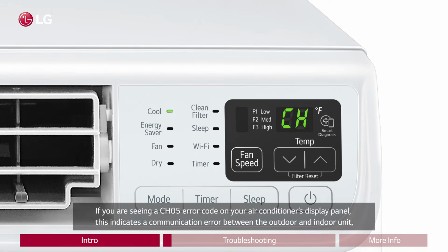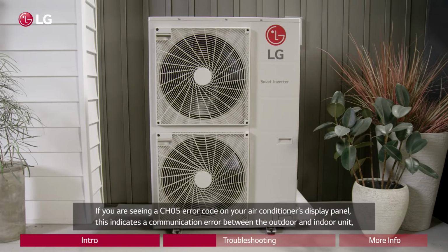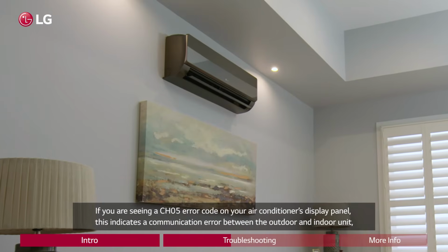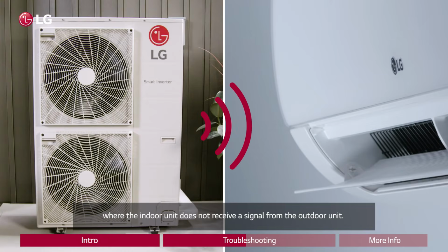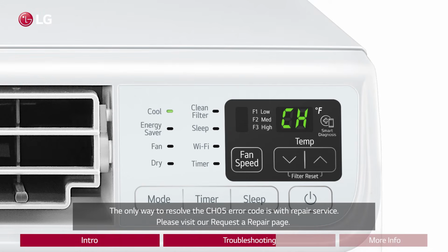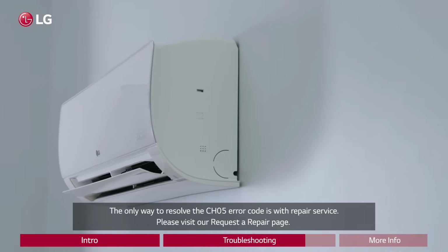If you are seeing a CH05 error code on your air conditioner's display panel, this indicates a communication error between the outdoor and indoor unit, where the indoor unit does not receive a signal from the outdoor unit. The only way to resolve the CH05 error code is with repair service.